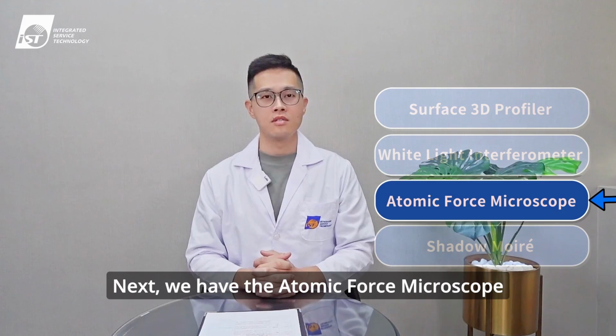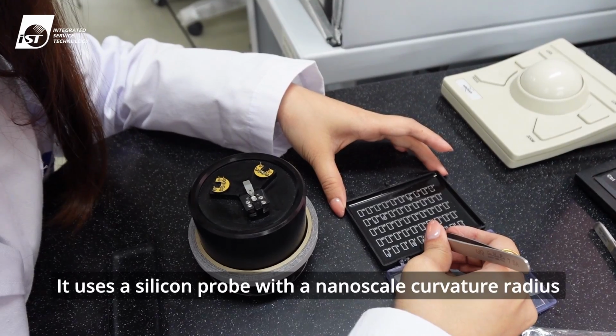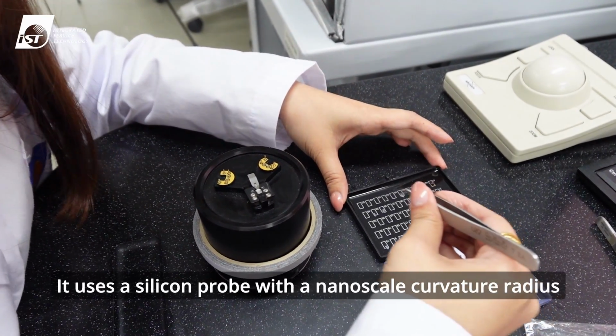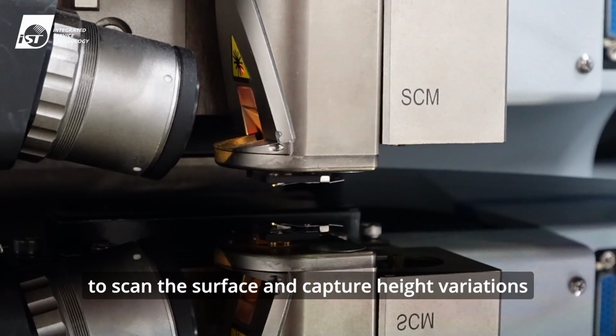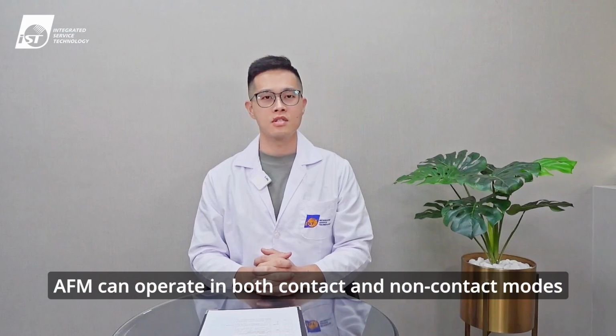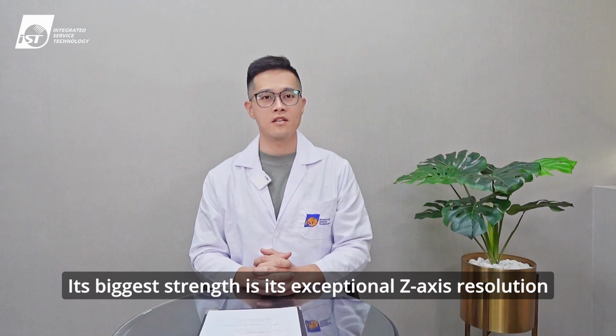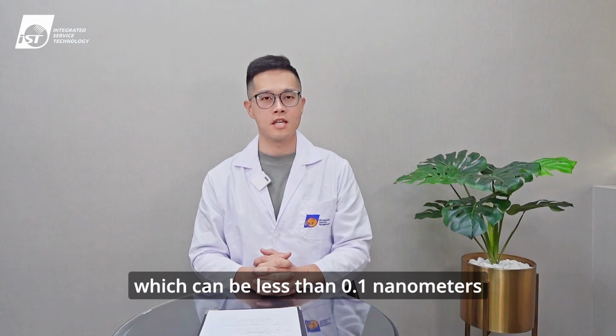Next, we have the atomic force microscope. It uses a silicon probe with a nanoscale curvature radius to scan the surface and capture height variations. AFM can operate in both contact and non-contact modes. Its biggest strength is its exceptional z-axis resolution, which can be less than 0.1 nanometers.